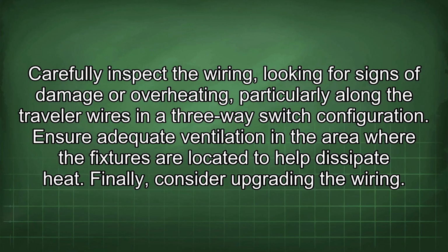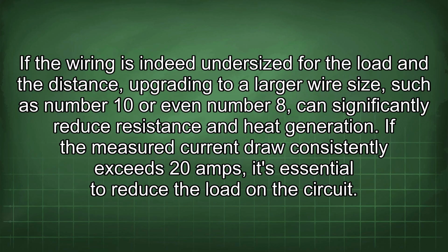Finally, consider upgrading the wiring. If the wiring is indeed undersized for the load and the distance, upgrading to a larger wire size, such as number 10 or even number 8, can significantly reduce resistance and heat generation.